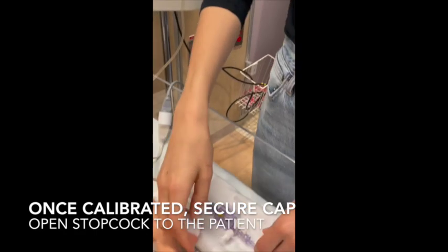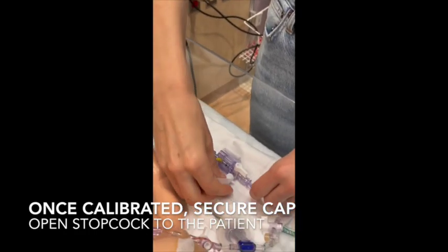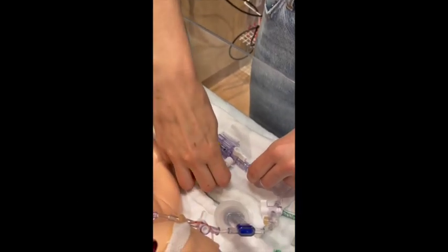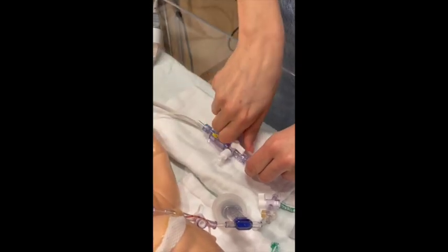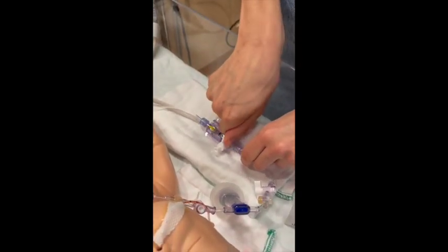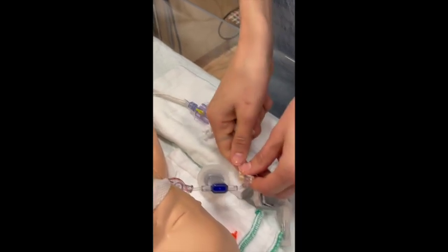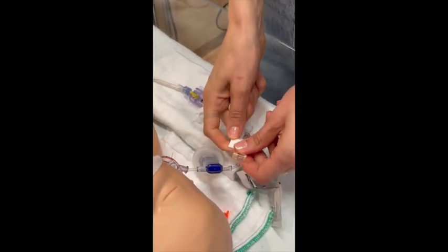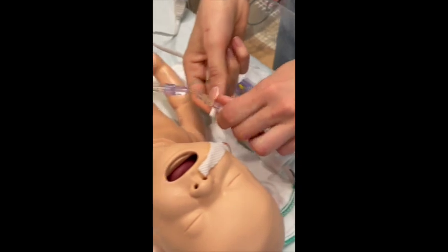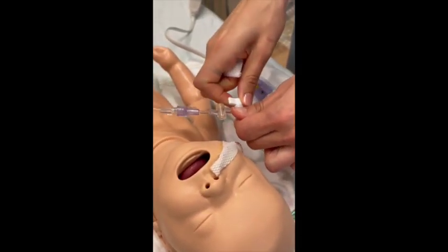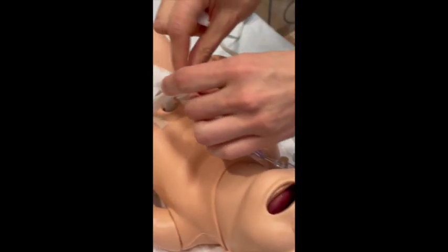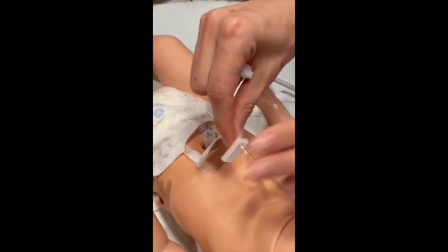Secure the dead end cap on the transducer head and open the stopcock to the patient. Unclamp the arterial line to the patient by either unclamping the extension set or by turning the valves on the VAMP Junior open, turning the valve parallel to the line. Verify adequate waveform. Document that calibration has been done.